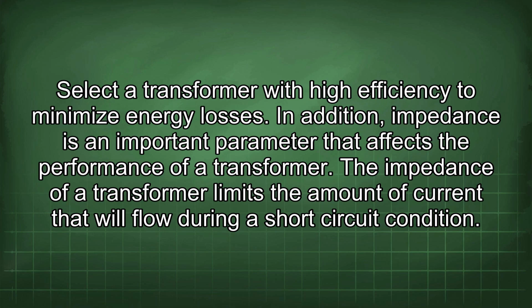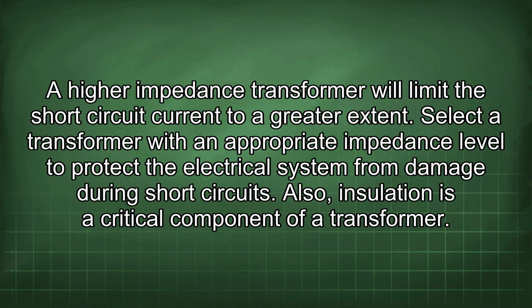In addition, impedance is an important parameter that affects the performance of a transformer. The impedance of a transformer limits the amount of current that will flow during a short-circuit condition. A higher impedance transformer will limit the short-circuit current to a greater extent. Select a transformer with an appropriate impedance level to protect the electrical system from damage during short circuits.